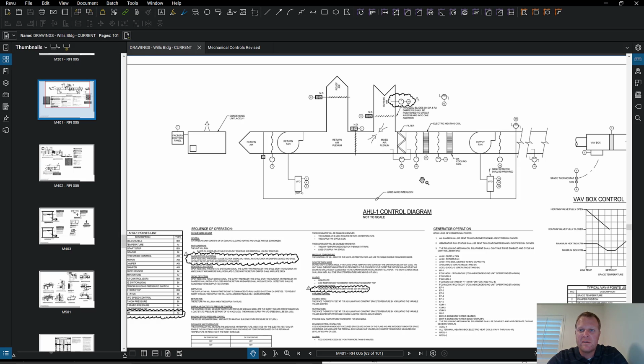you can actually follow up on the activity rather than, hey, how are we looking on the pressure on the mechanical piping? Oh, good, we passed our pressure test. Okay, well now you have to realize that there are more steps involved before you can go turn the boiler on, because the piping needs to be there before the boiler can get going. Because how are you going to start a boiler that doesn't have any water in it? How are you going to start a boiler with water in it if you can't move the water somewhere? It's going to immediately turn on, warm up, and then immediately shut off.